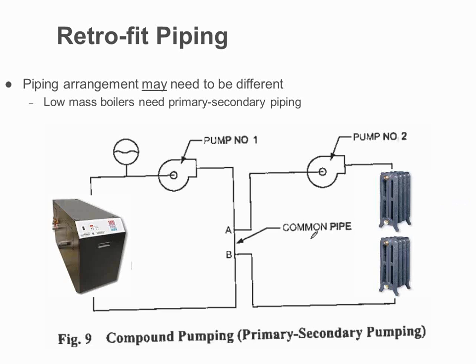Okay, and this shows you here. The biggest thing with that common pipe space there is that it has to be as small as possible. The normal rule of thumb is 4 pipe diameters. So if that boiler pipe is, let's say, a 2-inch pipe, A to B has to be a maximum 8-inch center line to center line. It has a lot to do with primary, secondary piping. We don't have a lot of time to get into it today, but keep those T's as close as possible. Maximum 4 times the pipe diameter. You'll have no issues.